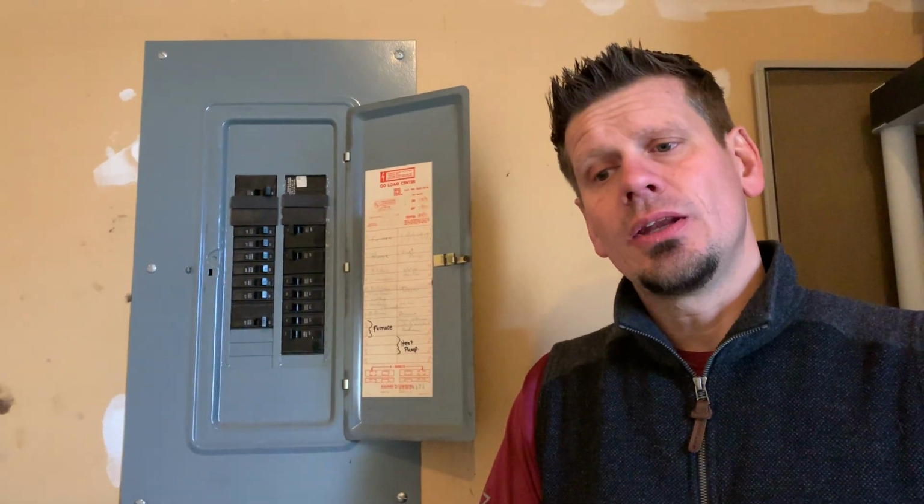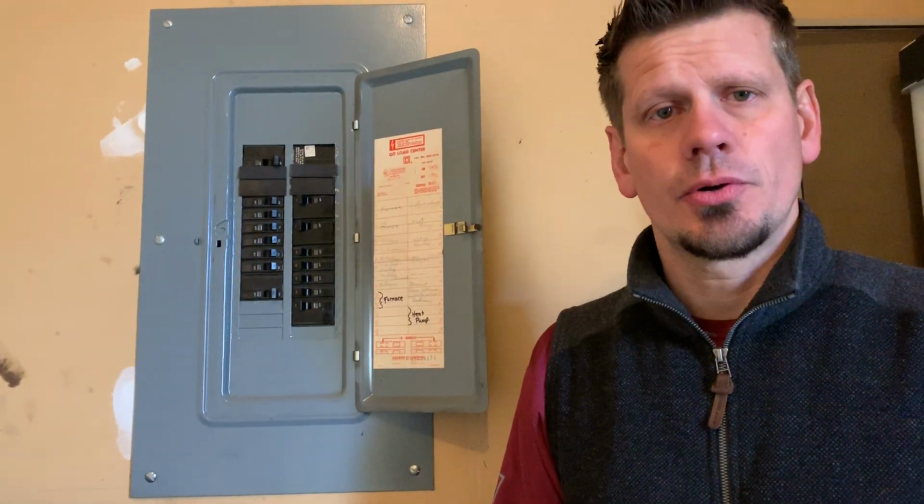The other thing I've seen in the past about why my energy bill is so high are very fluky things. For instance, a wire in the back of those baseboard heaters can ground out. And if it grounds out and yet the ground isn't detecting it to trip the breaker, that can cause the current to rise as well, because the appliance is then completely energized. I've seen it on dryers as well as electric ranges, especially those old coil top cooktop burners.